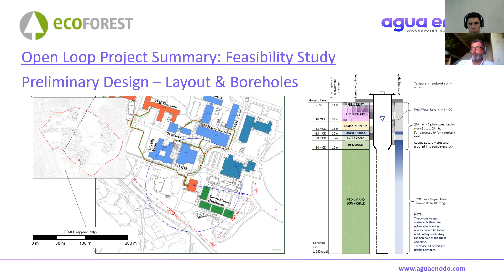The contribution of an open loop borehole comes with some uncertainty, so we try to give a range of possible heating and cooling loads. Here I've shown a table with peak heating and cooling loads, a range of possible delta T's between abstraction and injection temperature, a range of COPs, and most importantly, three rows at the bottom putting some probability on the likelihood of getting a certain flow rate out of the ground. At this site, we thought the best chance would be to start the design assuming you'd get 20 litres a second out of 2 pairs of open loop boreholes—4 boreholes in total, 2 abstraction and 2 injection. That would be the most likely scenario, with a certain kilowatt peak load it could supply.